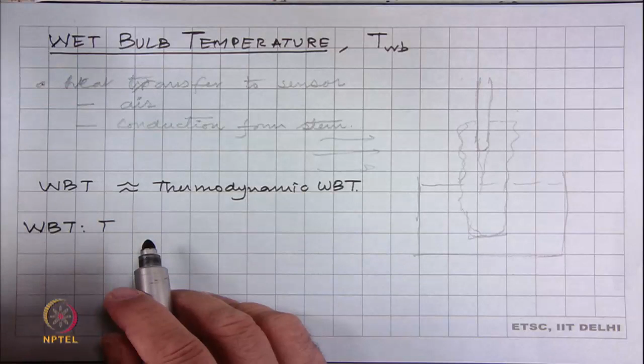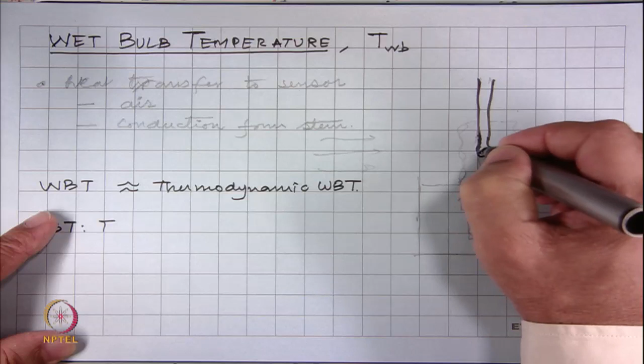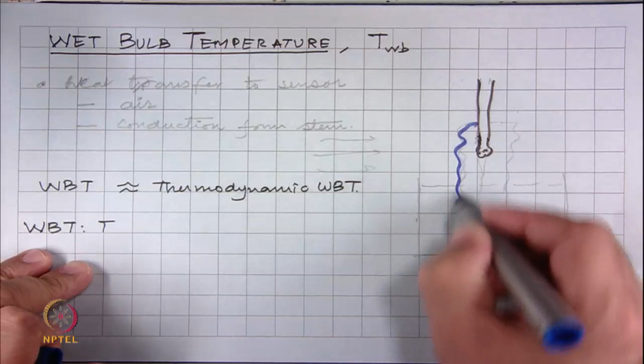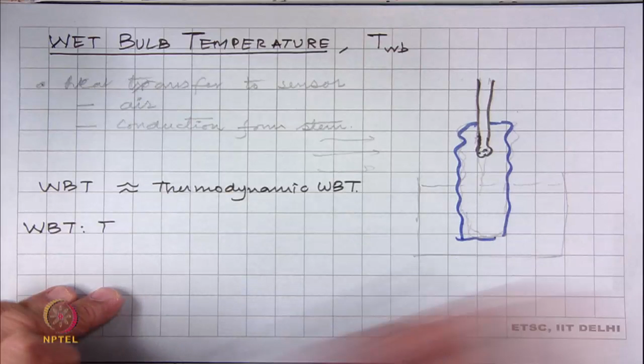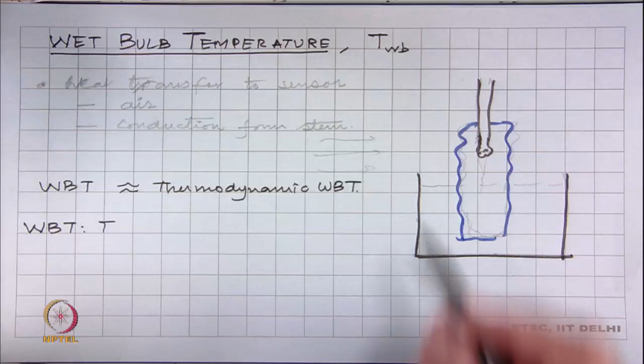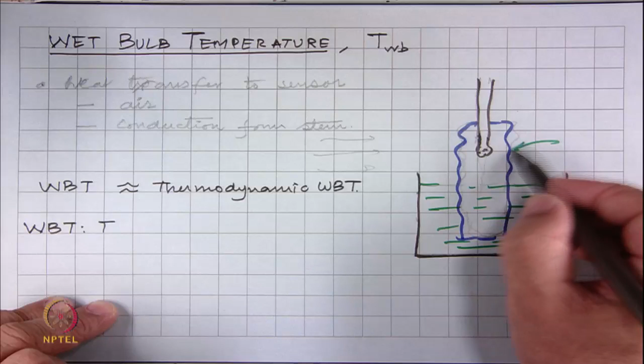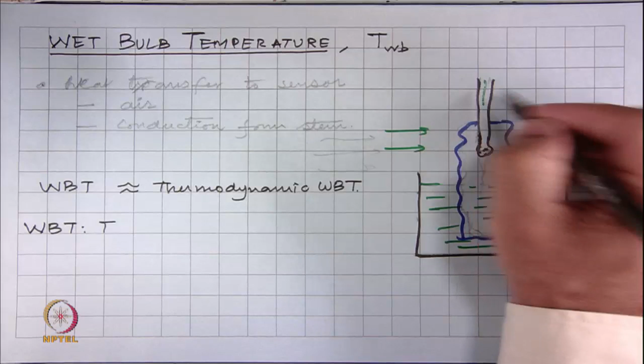TWB, which is what we measure in a lab, where we take a sensor and we take this sensor and wrap around it a porous cloth, a fibrous material, all of which is kept in a container which has got liquid water in it. So, this is all liquid water, and this is what we can call it as a wick or a porous fabric, and this will let it remain in air or blow air slightly over it. As the water evaporates, it generates a saturated condition, and the temperature indicated by this is what we call the wet bulb temperature, or TWB, or often called WBT.